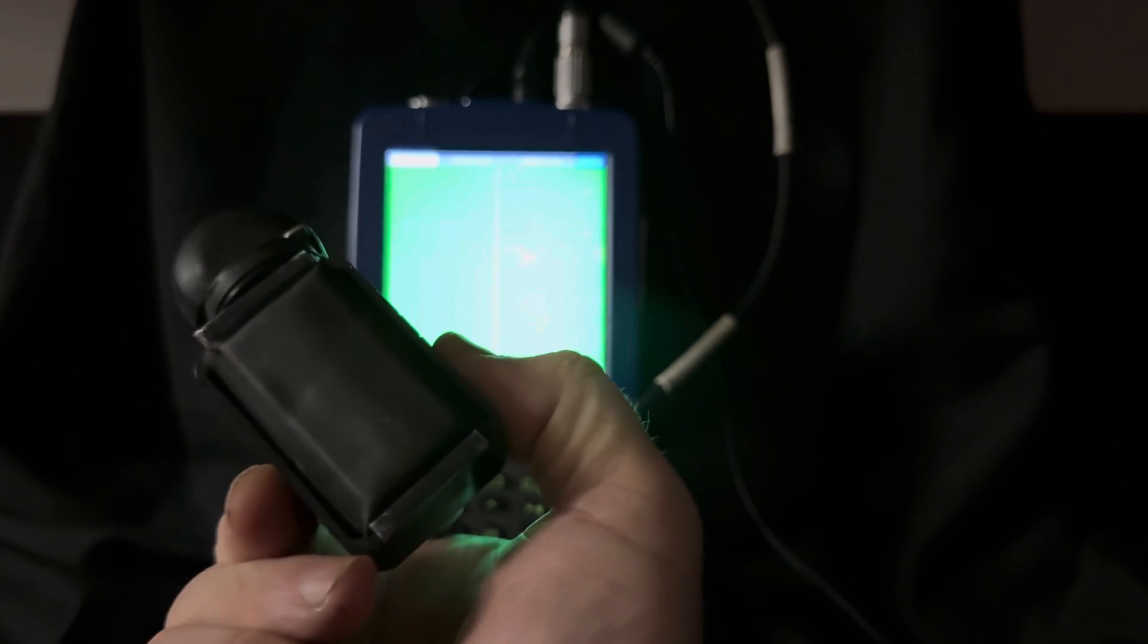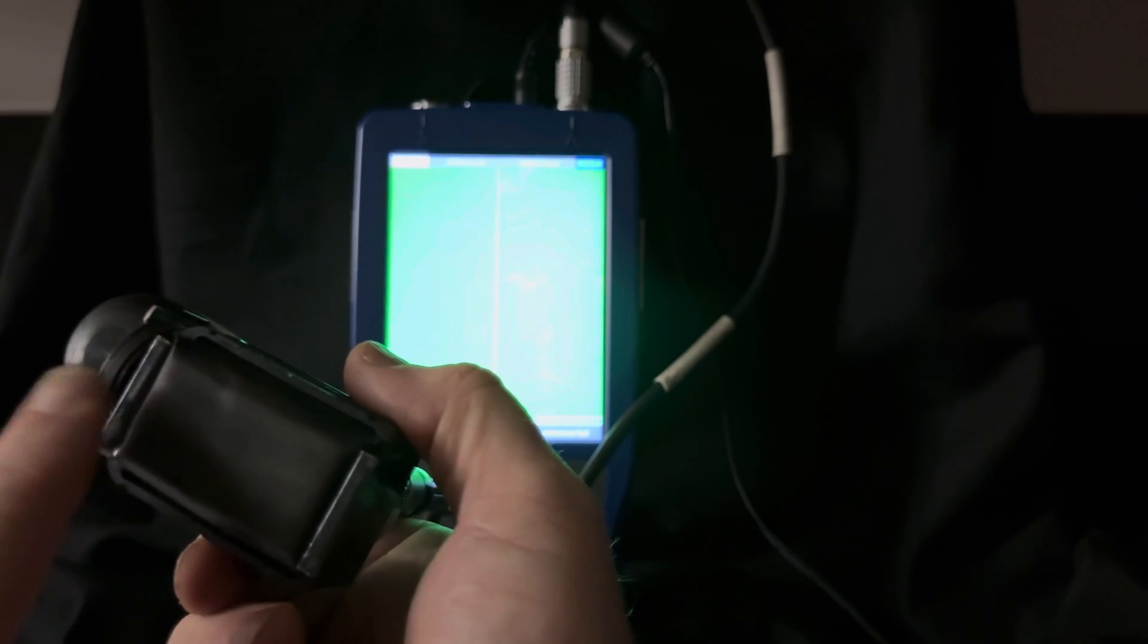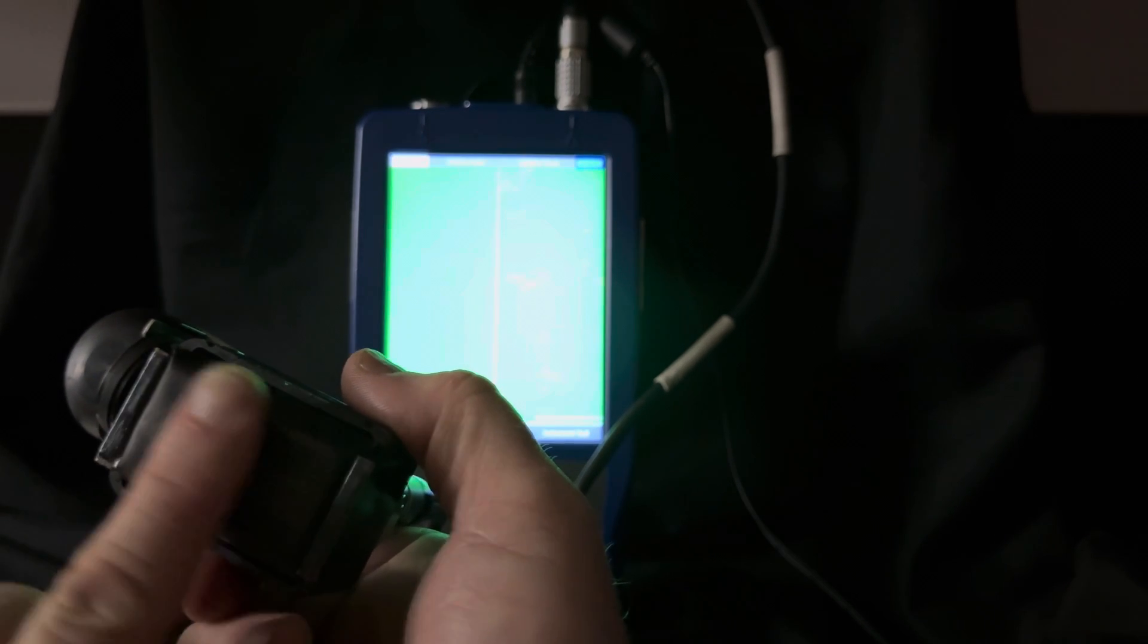Now one of the nice things about array probes, look at the coverage that you get here. There's many coils in here and you get 100% coverage in this area.